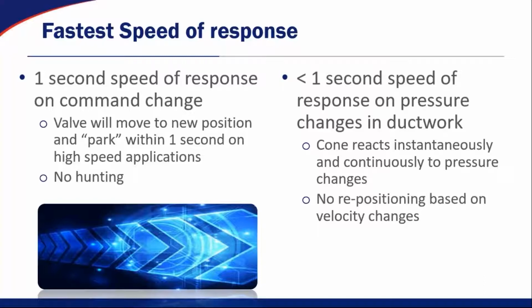And there's some ambiguity to the standards that happen inside of wet chemistry labs. Usually people will say it's about a 3-second speed of response from the sash's last position, but 1 second is better. And the reason they have those 3 seconds or so is because they can't make the guidelines favor one manufacturer. And because Phoenix is the only manufacturer that actually gives you a 1-second speed of response from command change, they can't really write the guidelines to favor us. However, competition, when they talk about speed of response, they'll usually say about 3 seconds from final position of the fume hood sash, which means that we're still within the guidelines. But again, Phoenix controls 1 second speed of response to command change.